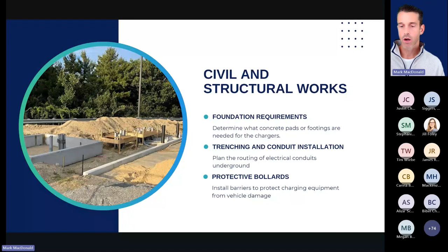Typically they're all top anchored, so you can move them around, but you've got to have the appropriate mechanical equipment there to do it. Trenching and conduit installation, there's some complex routing sometimes from pad mount transformers, from pole mount, depending on how you're feeding these. And very importantly, which sometimes gets overlooked, those protective bollards. We're not all the best drivers. We want to make sure that equipment is protected, because it is a large cost to invest in and deploy it, as you saw earlier.